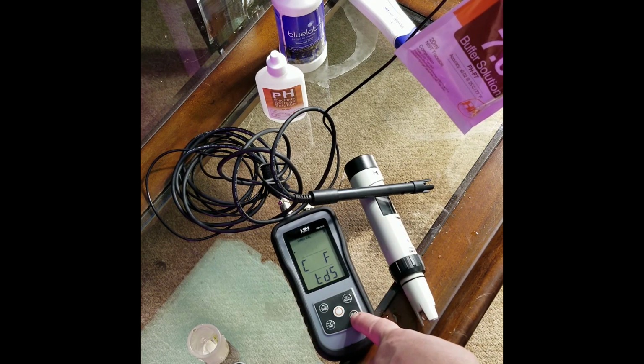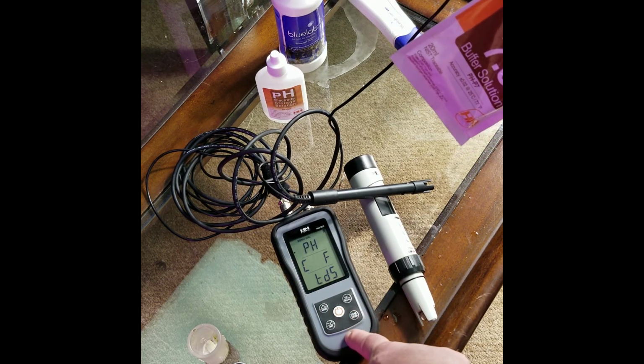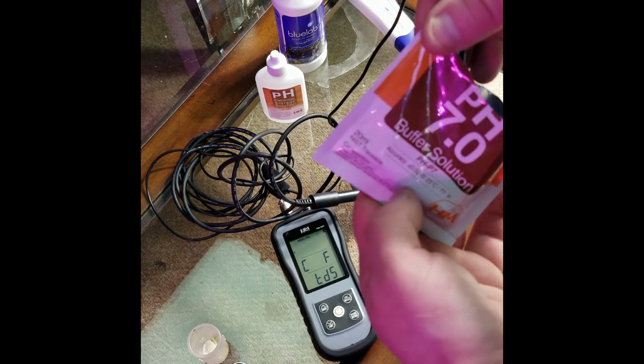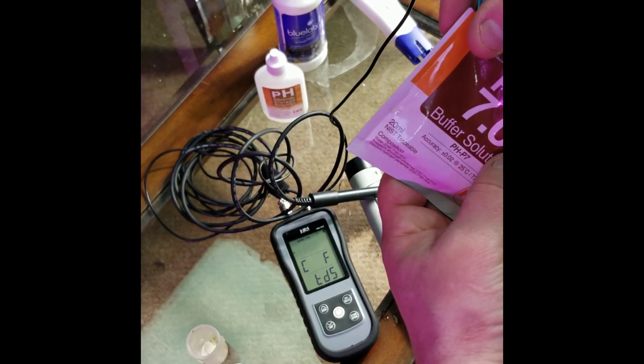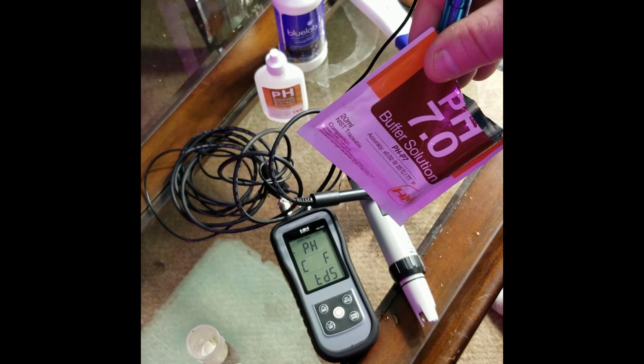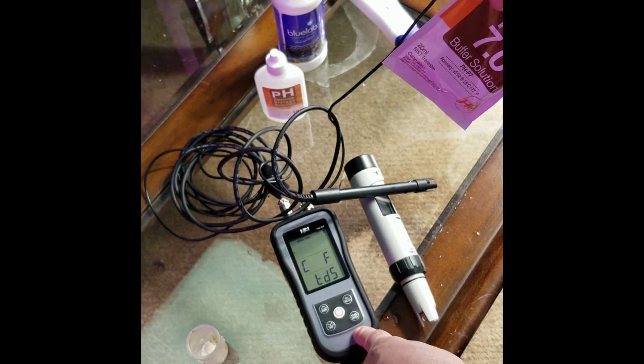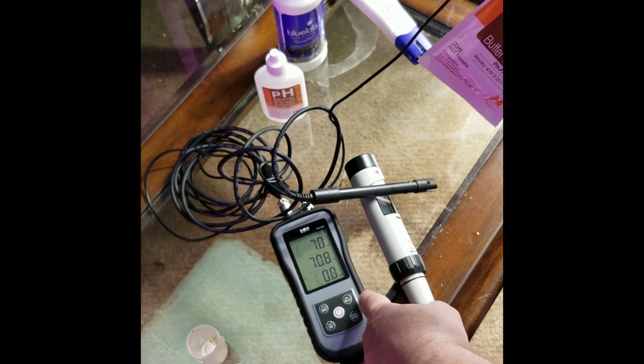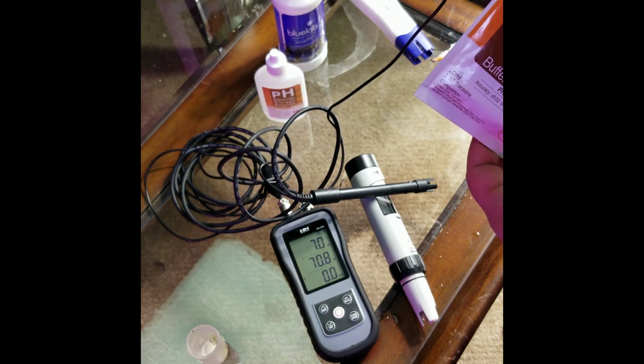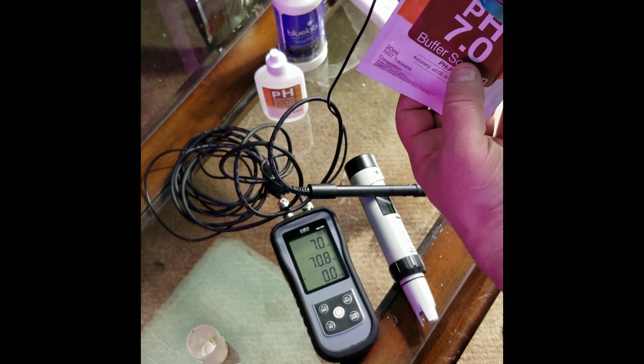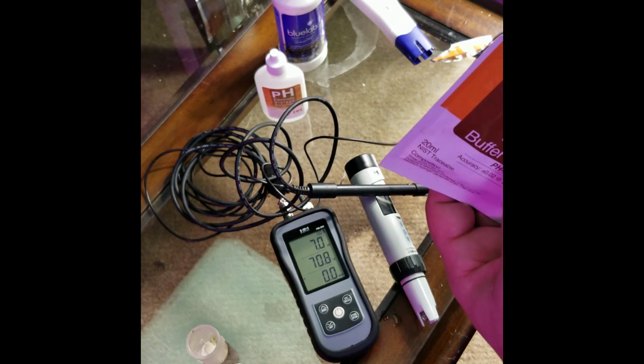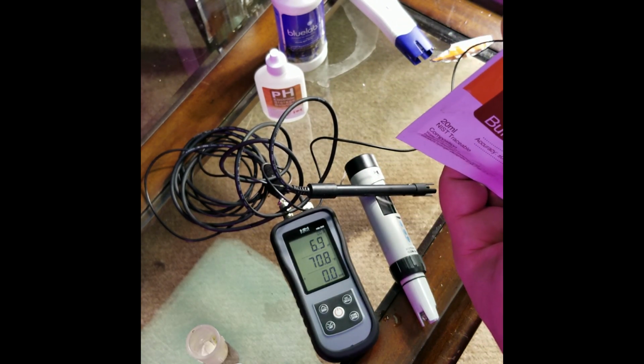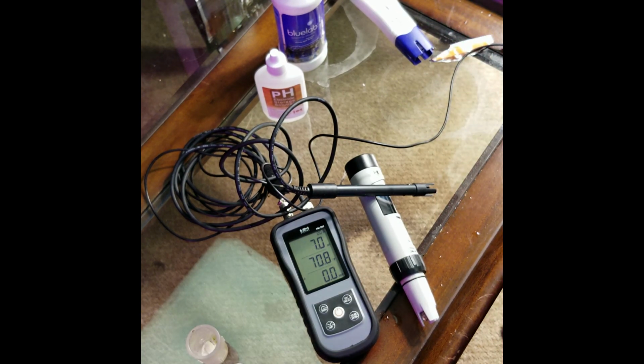And what that probably did, I'll keep this in here, is because I was moving it around, it probably did jump up by 0.1, and so it threw the error. This time it didn't, and so we just hit escape, and escape again, and now it's deadlocked at 7. So once you get past any first errors and you've got your 7 point set, that automatically adjusts your 4.0, your acidity. But you always have to calibrate your acidity.